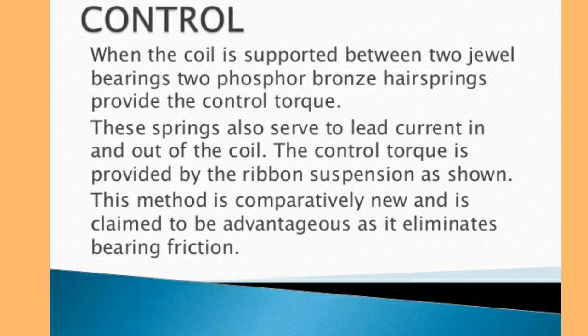Regarding the controlling part in PMMC instruments: the controlling torque is produced by two springs attached to the spindle. The springs are made of phosphorus bronze and placed between two jeweled bearings. The springs also provide the path for lead current to flow in and out of the moving coil — that is, the total current enters through one spring and leaves through the other.